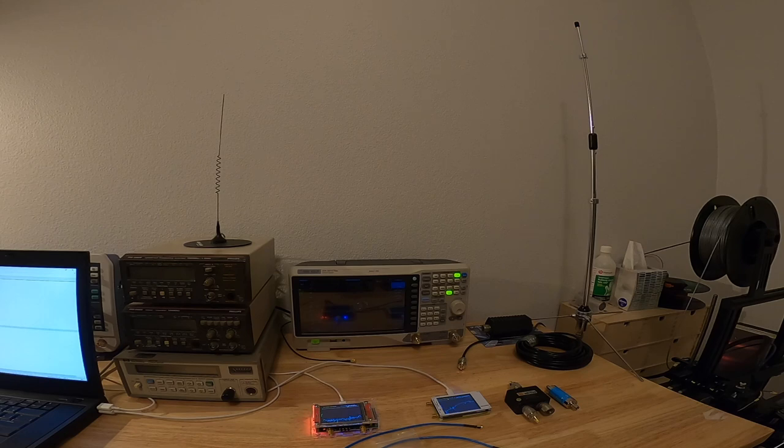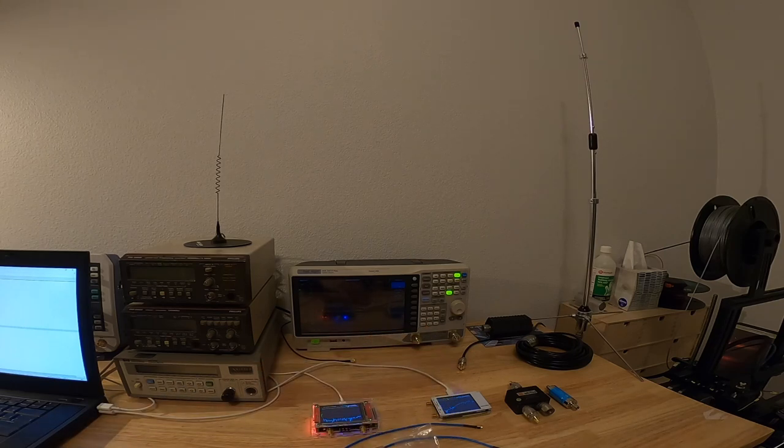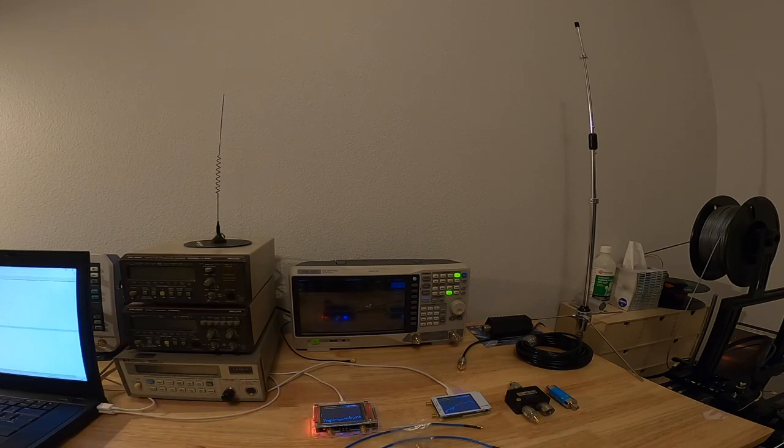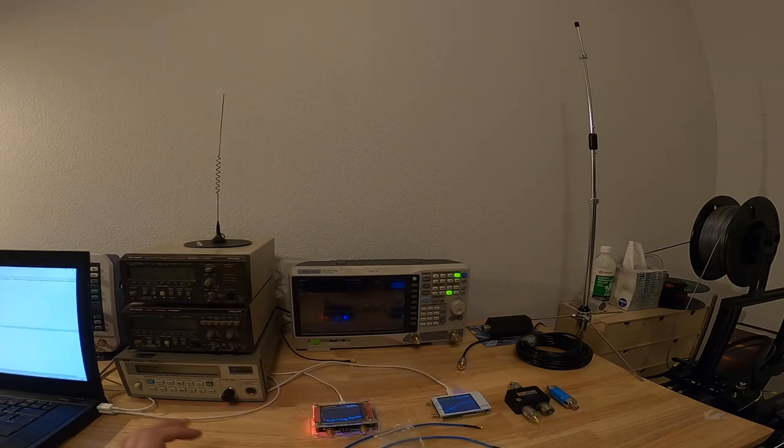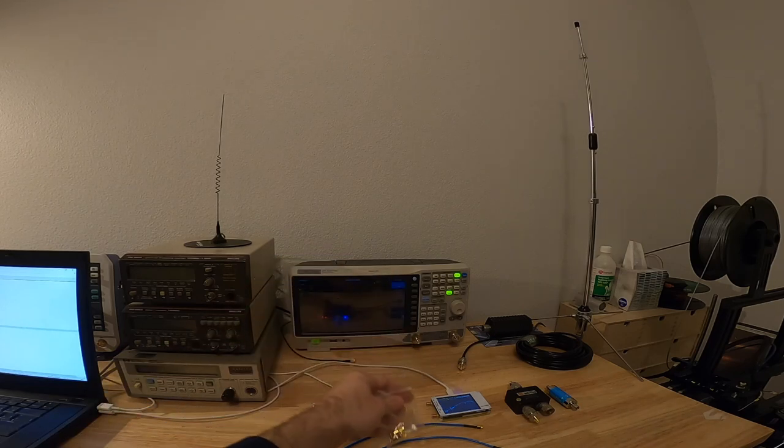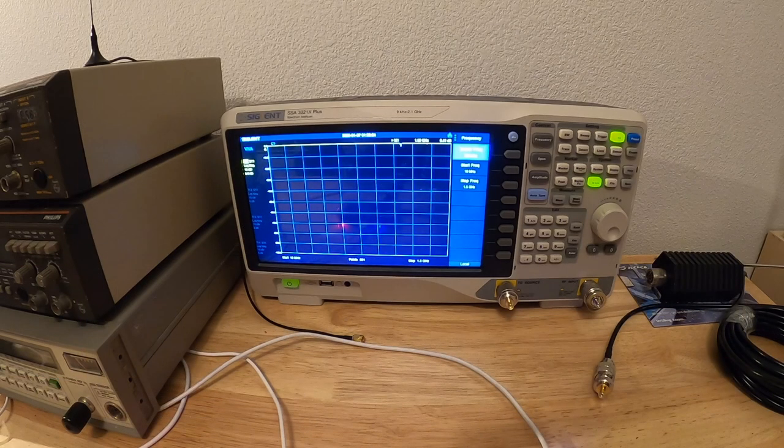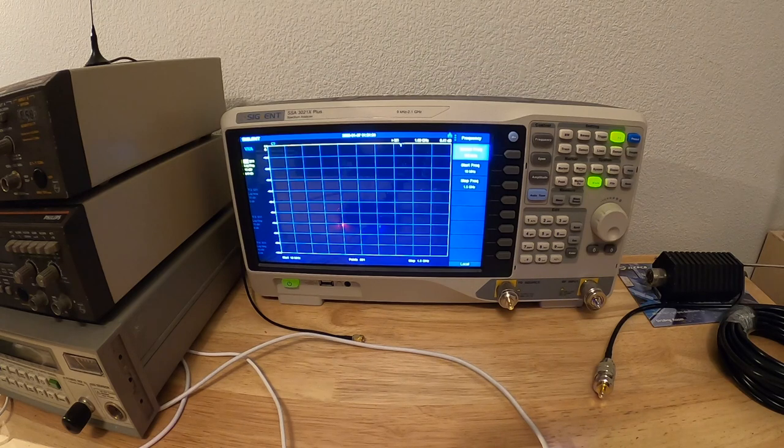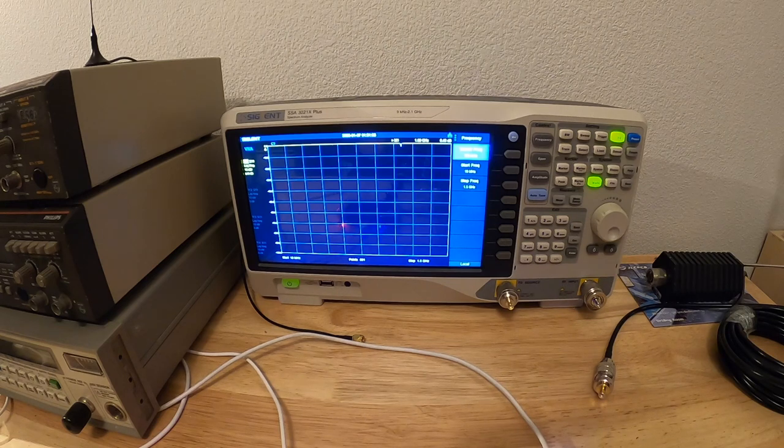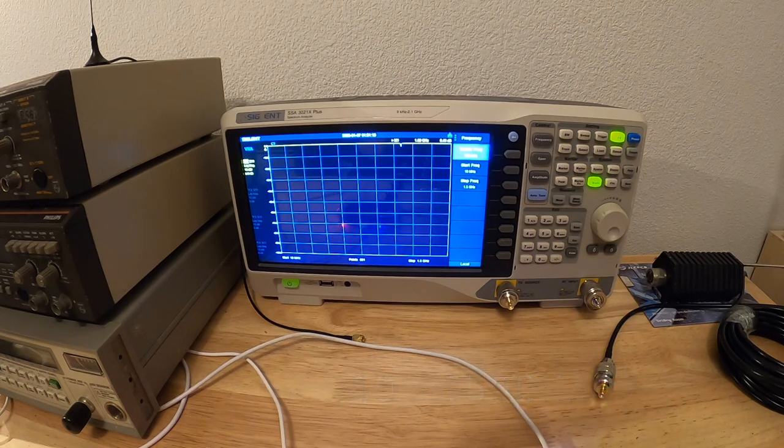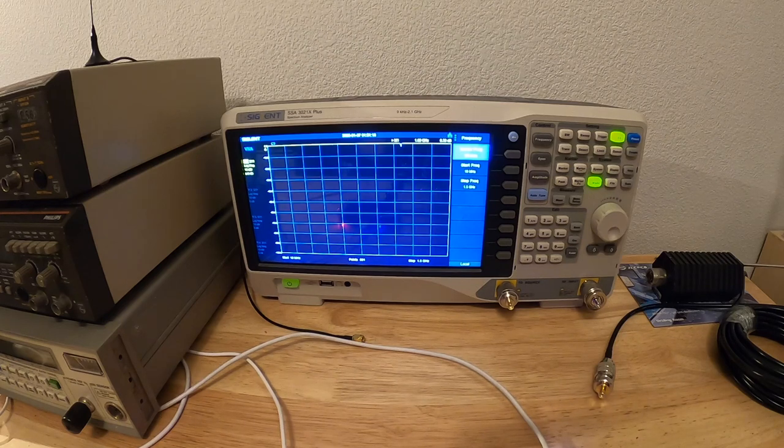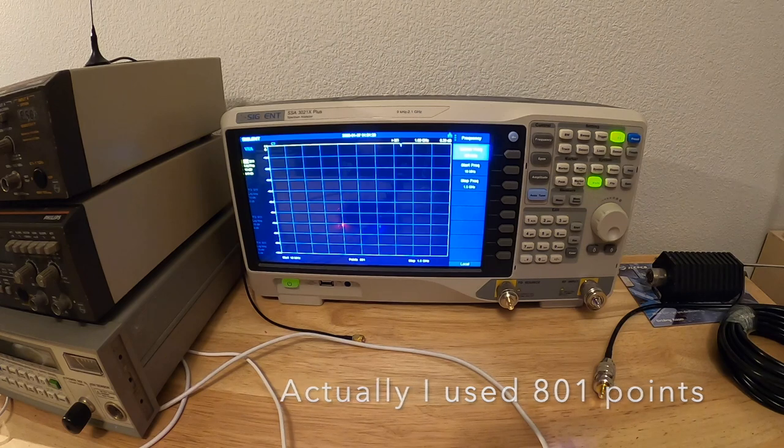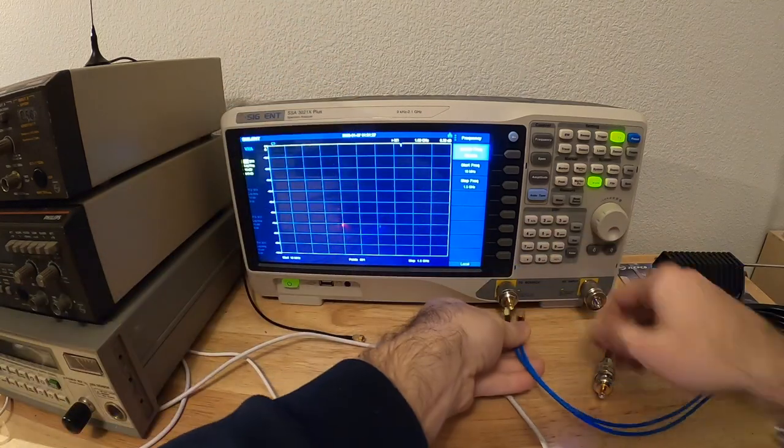The first step is to calibrate the VNAs using the same cables, the same calibration kit. The quality of those really doesn't matter because, as I said, we are comparing the instruments. We are not trying to qualify the calibration kit or the cables. As long as the short behaves roughly like a short, the load behaves roughly like a load, it should be fine. I did check offline. I compared the load in that kit with a few others and they're all spot on. Before starting, I need to decide what measurement parameters I'm going to use. Obviously, I'm going to use the same measurement parameters for all the different instruments. What I've chosen to do is to measure from 10 MHz to 1.5 GHz. All those instruments allow me to use 1024 points.